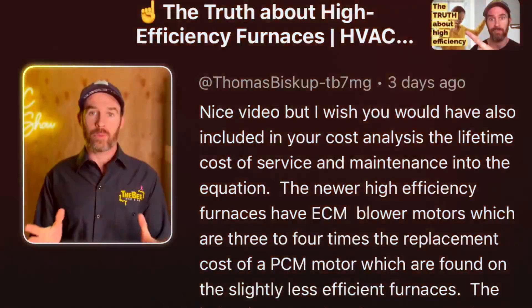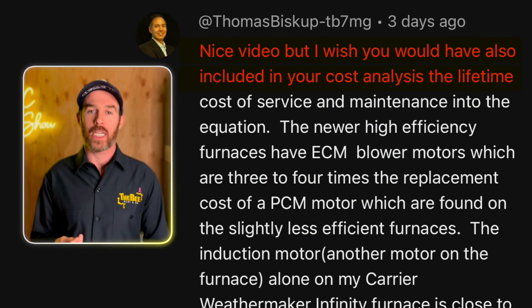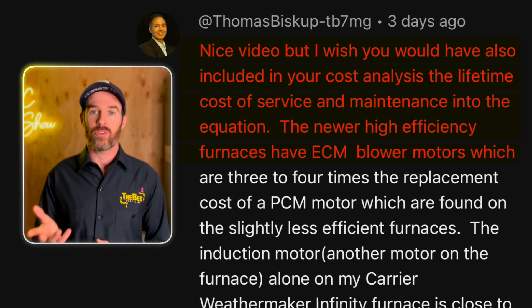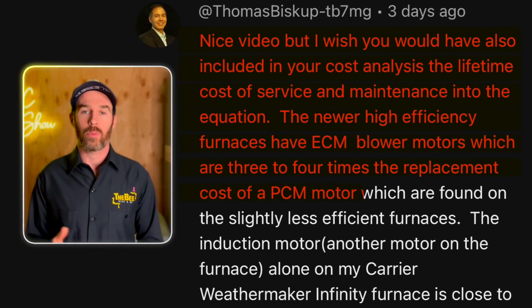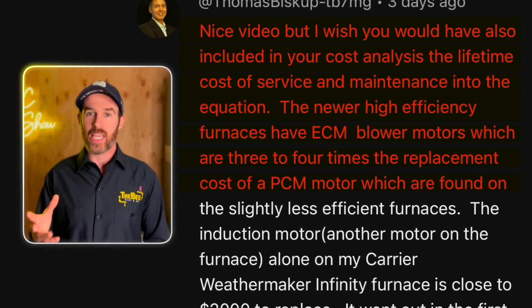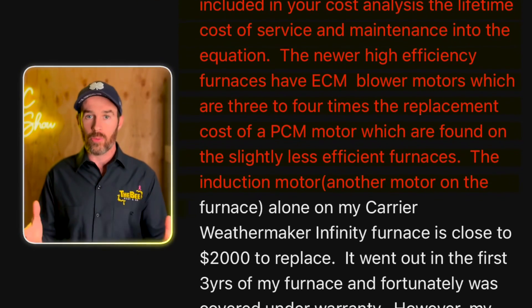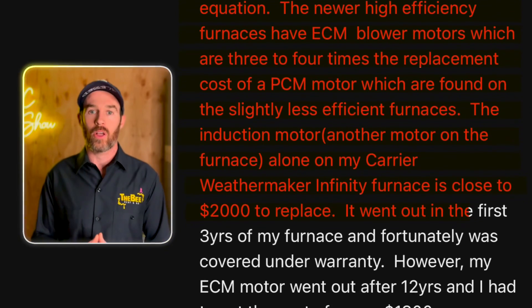The comment is somewhat long but I'm going to read the whole thing because it's also a first-hand experience. Subscriber Thomas wrote: 'Nice video, but I wish you would have also included in your cost analysis the lifetime cost of service and maintenance into the equation. The newer high efficiency furnaces have ECM blower motors which are three to four times the replacement cost of a PSC motor, which are found on the slightly less efficient furnaces.